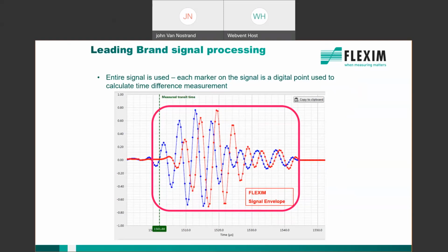So FLEXIM uses twice the transmit voltage of other ultrasonic meters as well. So with a higher signal amplitude, we're able to measure on really tough pipes that would otherwise be impossible. For example, thick sludge lines, ductile iron cement line pipes, precast concrete pipes. We're able to do these tough applications that were otherwise not even considered for ultrasonic.